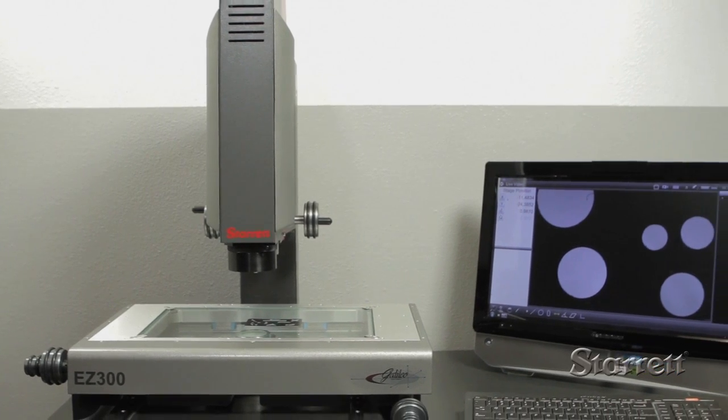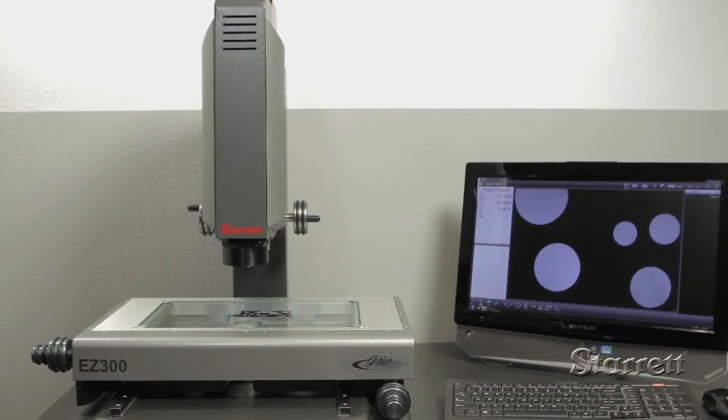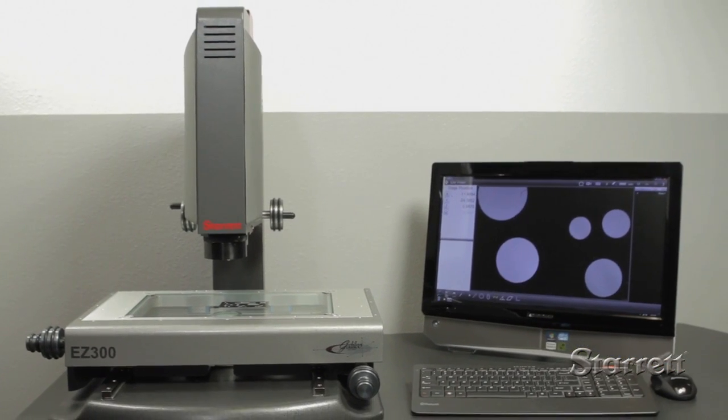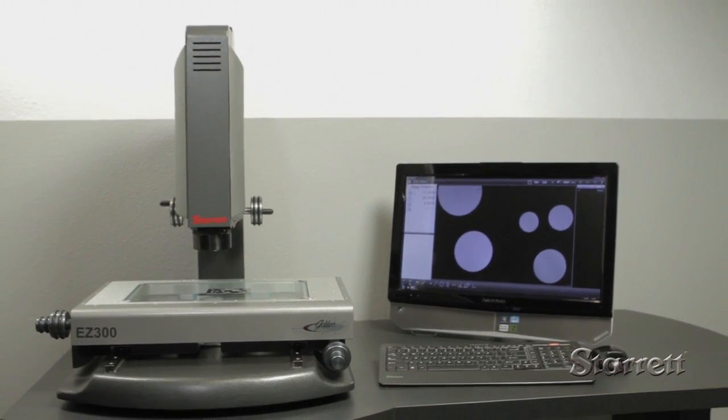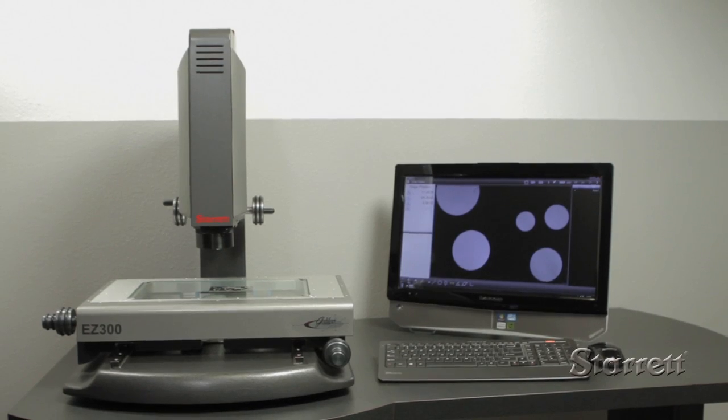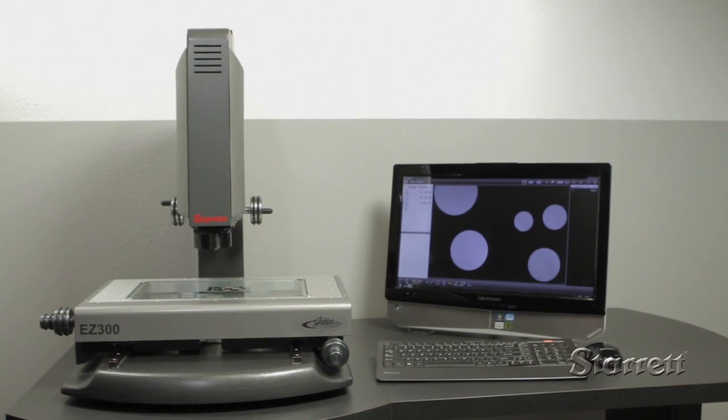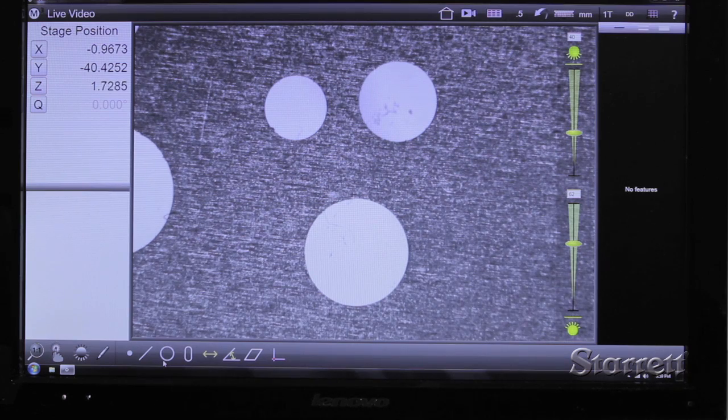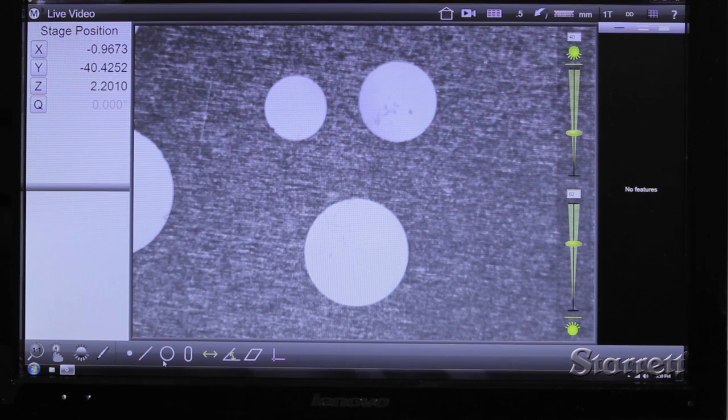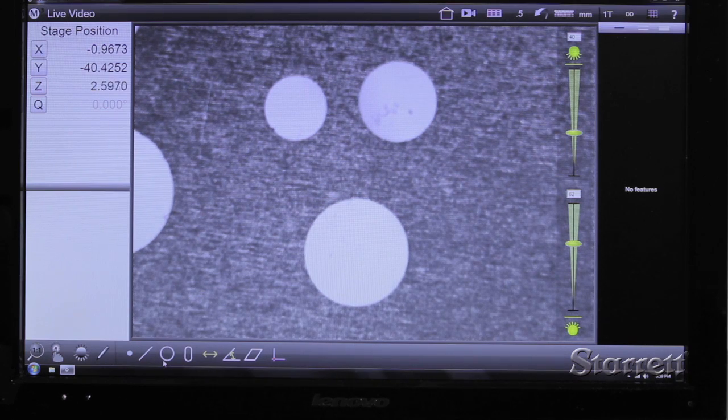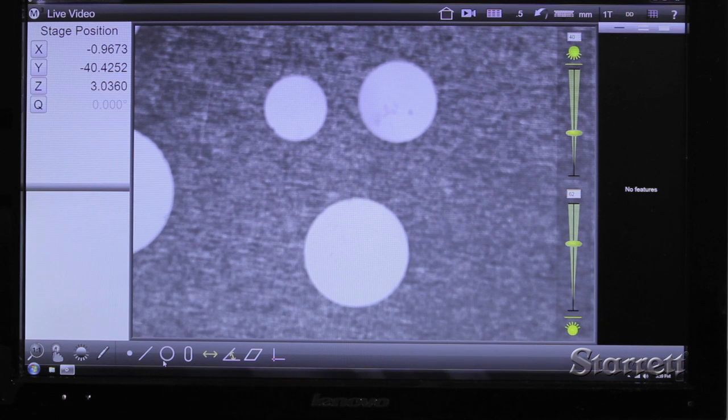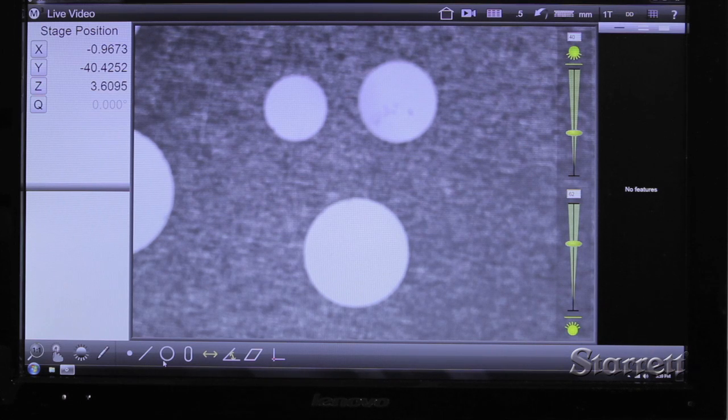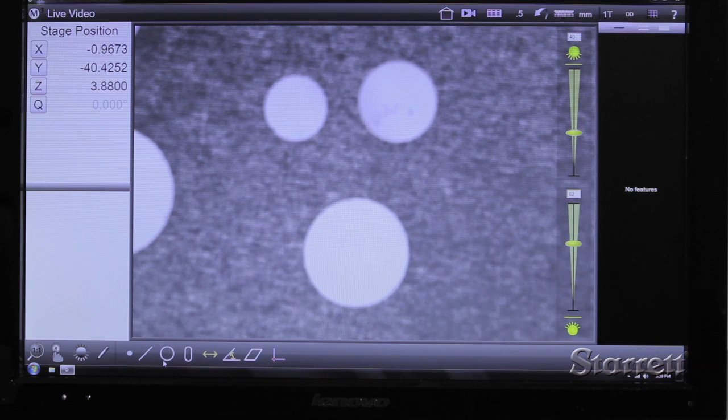Field of View or FOV has obvious benefits for video measurement. With a larger area, more features can be measured in a single setup. Historically, FOV has meant lower resolution and image distortion, so while the user can see more, there is a loss of accuracy.